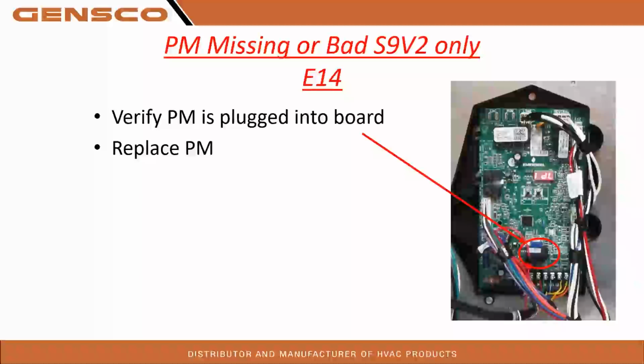If you have a new board and you put the personality module on and power cycle it, you shouldn't have a problem, unless there's a problem with that personality module, which you'd have to replace. They are serialized and orderable from the factory. It's not something we stock, because they're serialized to that specific piece of equipment. So you'll have to call down to your Gensco branch. They overnight them typically. So if you order them before a certain time, you'll have them the next day. They're very good about doing that. But most of the time, someone just replaces the board and has this error, and we simply tell the technician to take it off the old board and put it on the new one.